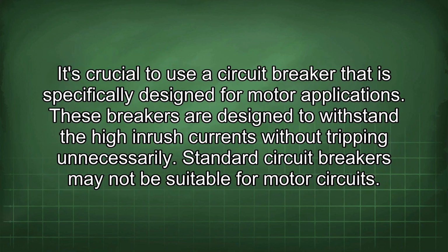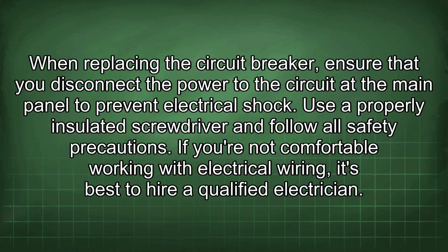It's crucial to use a circuit breaker that is specifically designed for motor applications. These breakers are designed to withstand the high inrush currents without tripping unnecessarily. Standard circuit breakers may not be suitable for motor circuits. When replacing the circuit breaker, ensure that you disconnect the power to the circuit at the main panel to prevent electrical shock. Use a properly insulated screwdriver and follow all safety precautions. If you are not comfortable working with electrical wiring, it's best to hire a qualified electrician.